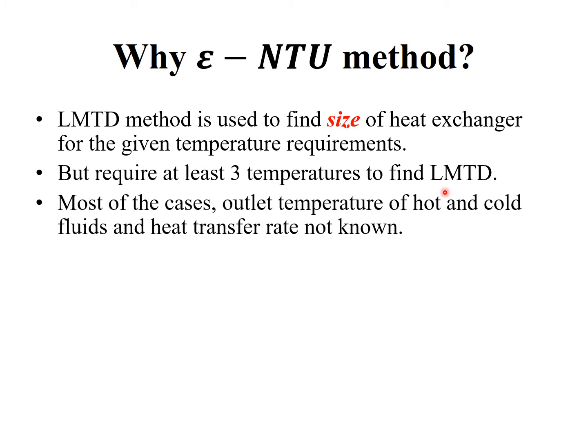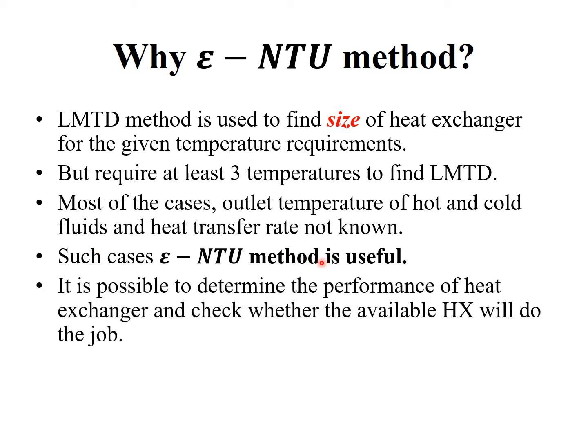LMTD requires at least 3 temperatures. But in most cases the outlet temperatures of hot and cold fluids are not known. Inlet temperature can be easily found, but outlet temperature depends on the performance of the heat exchanger. So when only inlet temperatures are known, we cannot use the LMTD method, and therefore the effectiveness-NTU method is used.